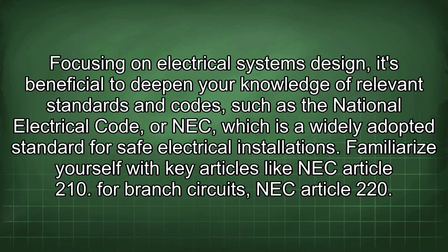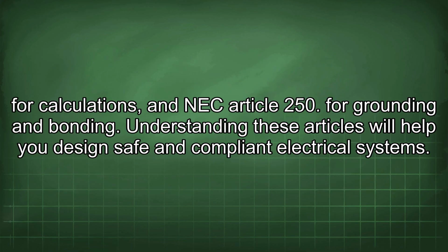Focusing on electrical systems design, it's beneficial to deepen your knowledge of relevant standards and codes such as the National Electrical Code, or NEC, which is a widely adopted standard for safe electrical installations. Familiarize yourself with key articles like NEC Article 210 for branch circuits, NEC Article 220 for calculations, and NEC Article 250 for grounding and bonding. Understanding these articles will help you design safe and compliant electrical systems.